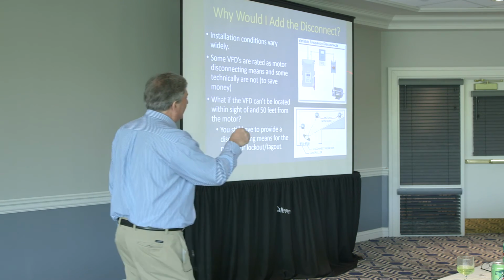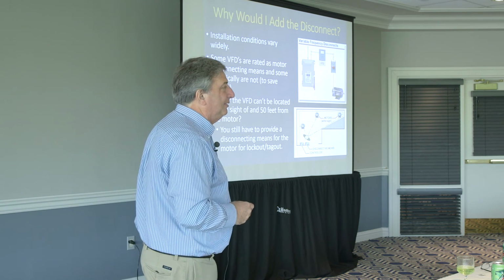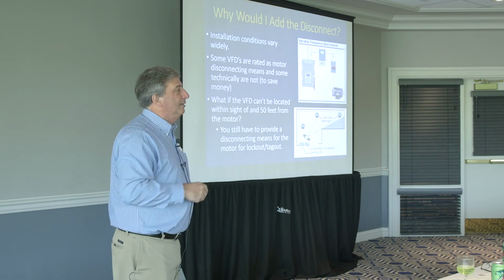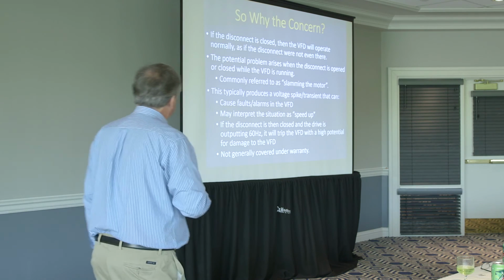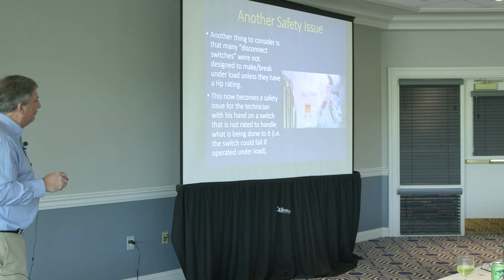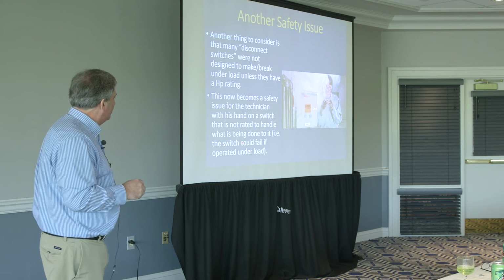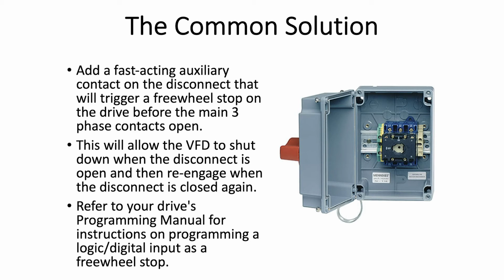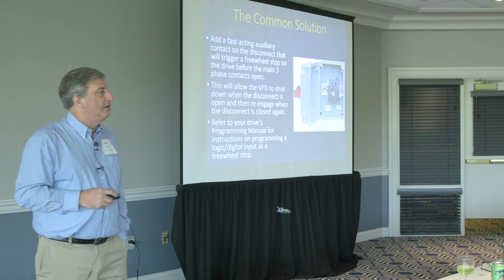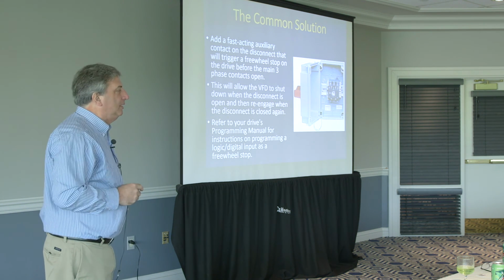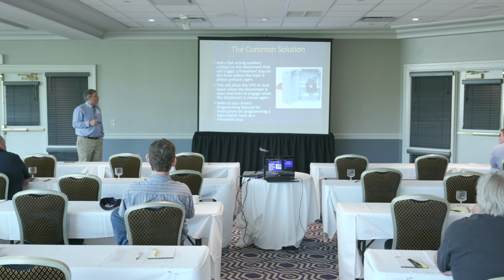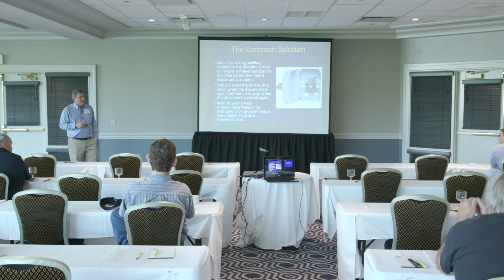And so depending on what that motor's driving and the inertia, you open up the contacts and the electricity, because of that inertia in the motor, is still arcing across those contacts. And that becomes a problematic situation. That's a safety issue for a technician with his hand on a switch that's not rated to handle what is being done to it. The switch could fail if operated under load. So the common solution is to add a fast-acting auxiliary contact on the disconnect that triggers a freewheel stop on the drive before the main three-phase contacts open. So this allows the VFD to shut down when the disconnect is open and then re-engage when the disconnect is closed again. And I avoid that slamming of the motor and the drive seeing a speed up condition and potentially getting to the point where I've got a problem. Refer to your drive's programming manual for instructions on programming that input as a freewheel stop when I do that.